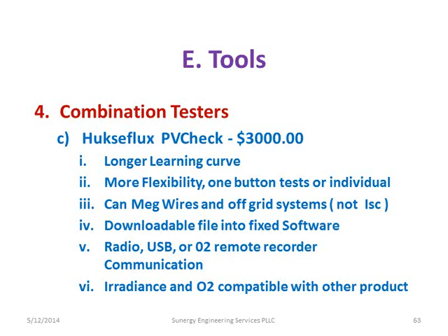You could go to the charge controller and connect to the wiring coming down from your array, even if it's series and parallel wired. You can't do short circuit current because it's only got a 10 amp rating, but it will meg each side of the array individually and automatically, which is really nice. They have their own software package, but it's hard to manipulate the numbers into your own report. You're kind of stuck with the way they format it, so that's one downside.